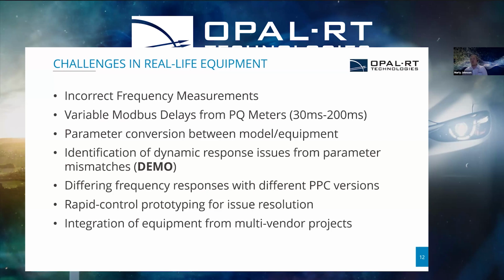The last part is that one of the largest sources of delays we see is the integration of equipment from multi-vendor products. This could be the SCADA developed by a different person than the PPC, different again from the inverter, or maybe we have hybrid systems. A lot of the time, most projects have at least some level of integration from different vendors. Part of the reason this can be an issue is that integration testing, like factory acceptance testing, only includes their own equipment, but rarely goes across the different vendors.